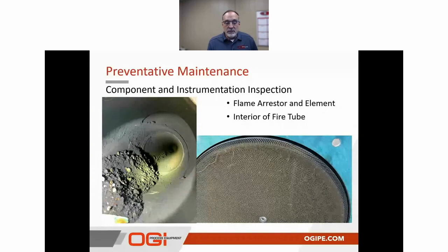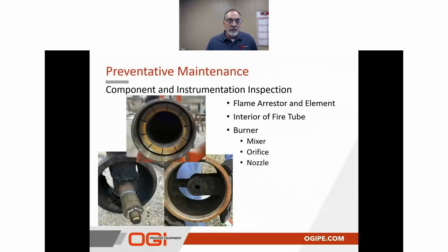Could also be discoloration caused by direct flame impingement of the main burner. We want to make sure that those items don't exist, and if they do, we need to make some modifications or changes to the setup of the burner, and obviously clean out the debris that may be in the fire tube. Next, we want to take a look at the burner.